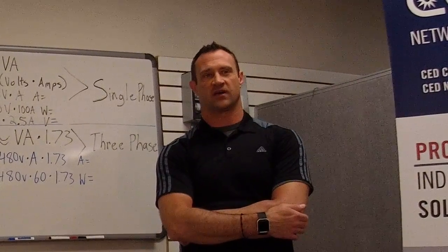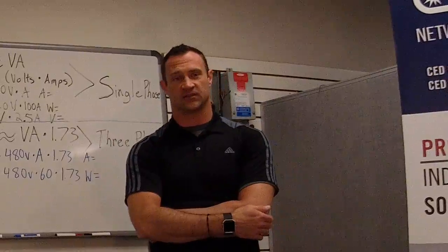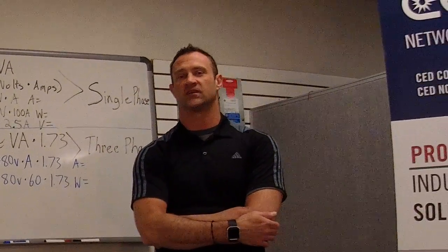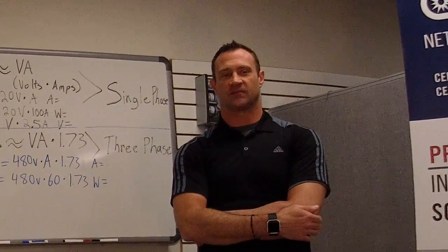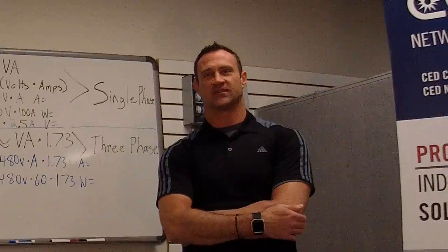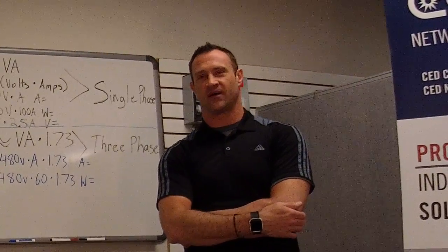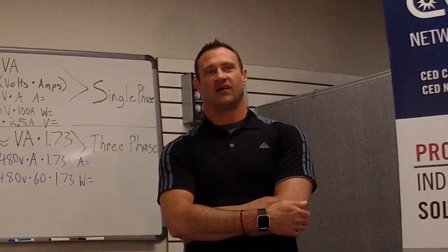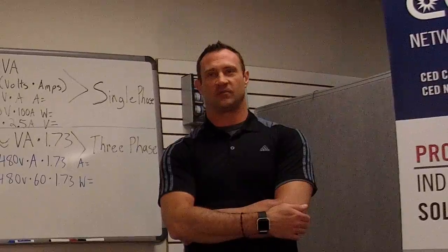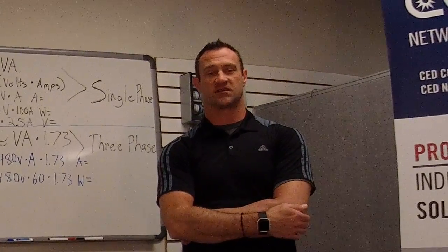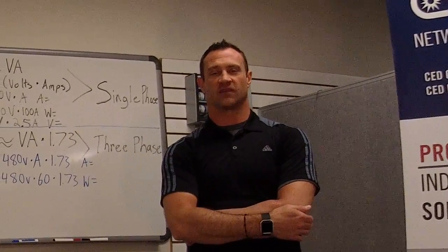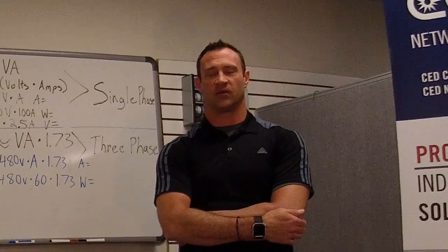This customer is pretty familiar and high-tech, but they wanted a little bit of help, so we volunteered to have myself and our tech consultant, our industrial control specialist, go to the job site, which happened to be outdoors in 12 degree weather with 10 mile an hour winds. We helped them out by hooking up software to the soft start and double-checked their wiring while they were checking the motor was coupled correctly and the pump was all set up correctly.